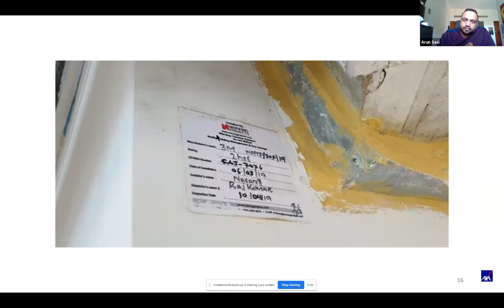Now, another part, the fire pumps. So obviously, because of the new Civil Defense Code, you've got everyone installing FM-approved dual-listed fire pumps, which is a great fact. But then this is a fire pump that's around 8 years old, right? So it's run a span of around 4 hours. Now, the reliability of this fire pump is hugely in question because, as an example, if you were to have a diesel car and if you run it 4 hours in a span of 8 years, would you really take it for a long drive? There are going to be issues that exist in the background that possibly cannot be seen until you do a proper test of the system.